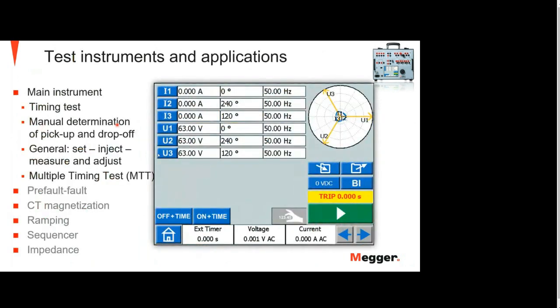So we have the main instrument. It looks like this. You can do a timing test. You can do determination of pick up and drop off of a relay, tripping contact. You can just set, inject and measure a voltage or current, whatever you would like to do. It's very easy to work here, very understandable, user-friendly. And here is the measuring of the time, for example. If you would like to save a test, you save it here. If you would like to open a saved test, you can open it from here.